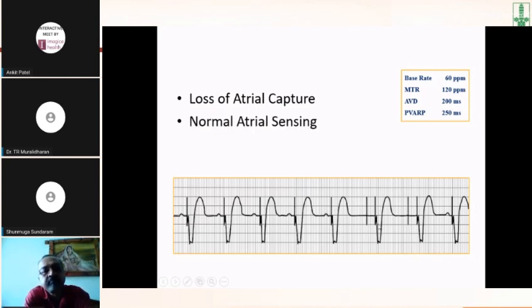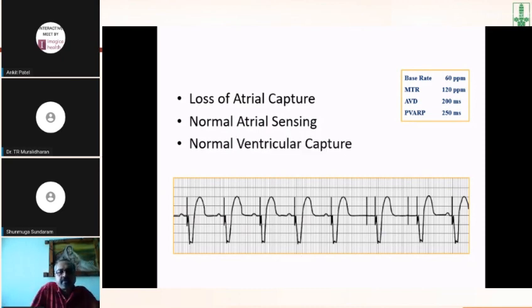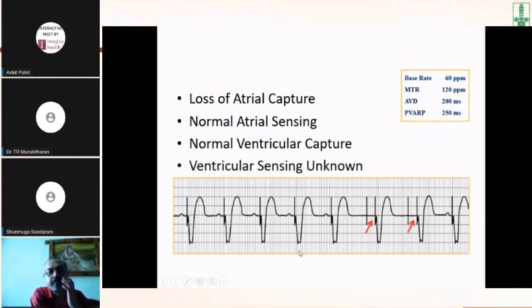Click, please. So sensing is probably normal, but in the sixth and seventh complexes, there's a pacing spike on the atrium, but no capture. Next, please. So normal ventricular capture. Next, please. And we do not have an idea about the ventricular sensing because all the ventricular events are captured by a pacing spike. And those two arrows show clearly loss of atrial capture after the first few beats, which have shown a normal atrial sensing. Next, please.